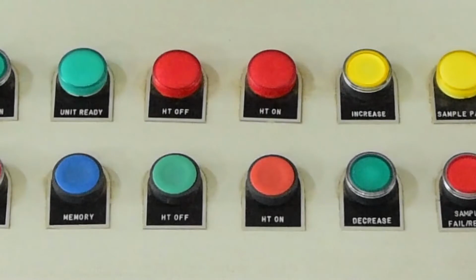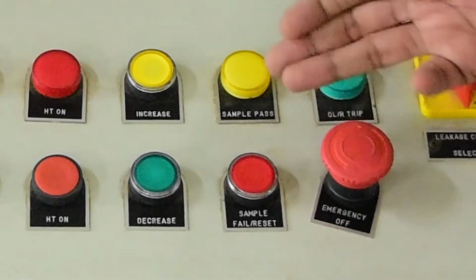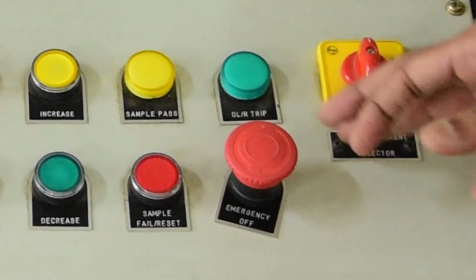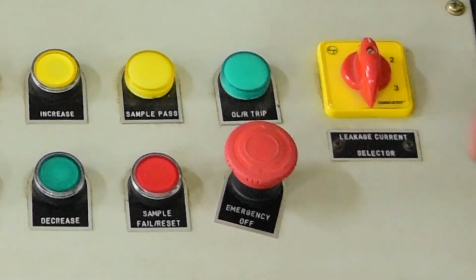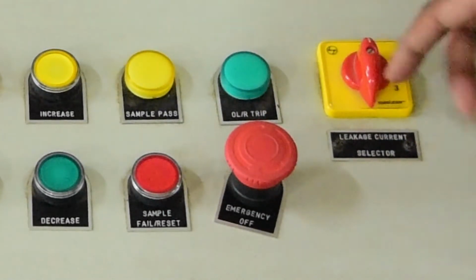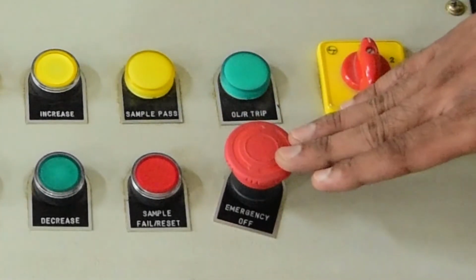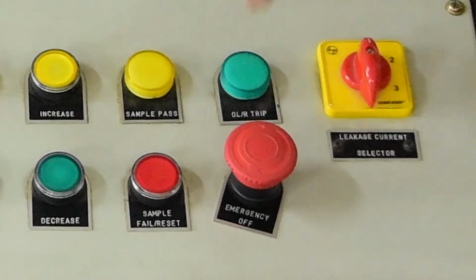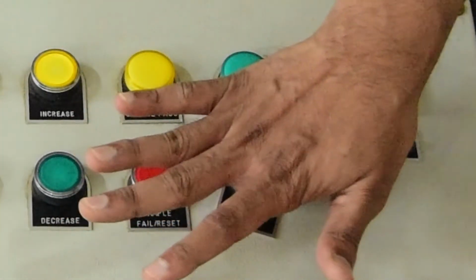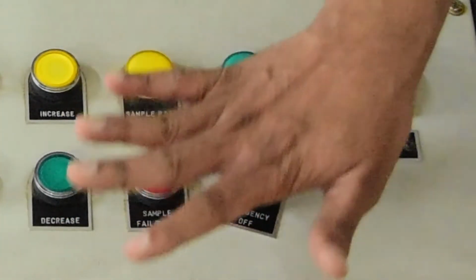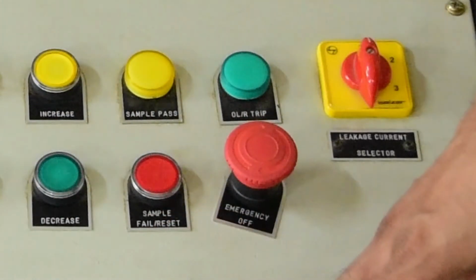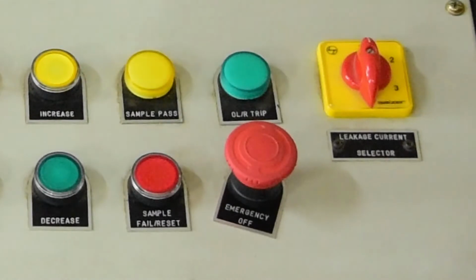Then the rest of the switches on the right hand side are sample pass, sample fail, then overload trip, and leakage current selector. There are 3 ranges here, and then this larger switch is an emergency off. Whenever there is something wrong with the unit, or some fire hazard, or something fails unexpectedly, this has to be pressed, and the whole supply will be disconnected for the safety of personnel as well as the equipment.